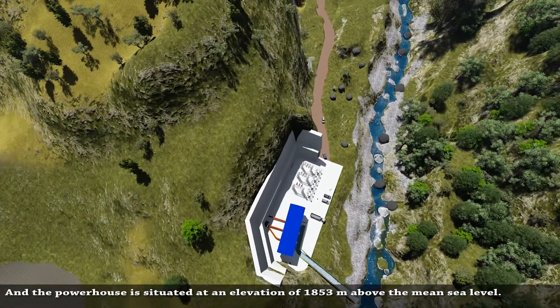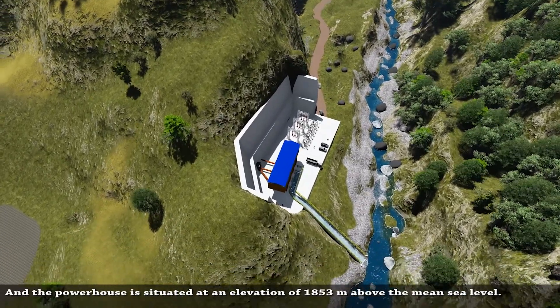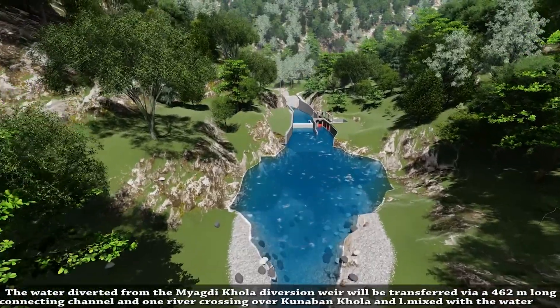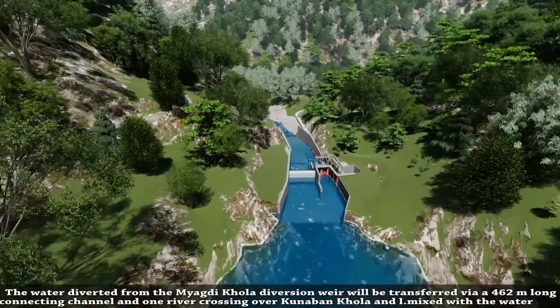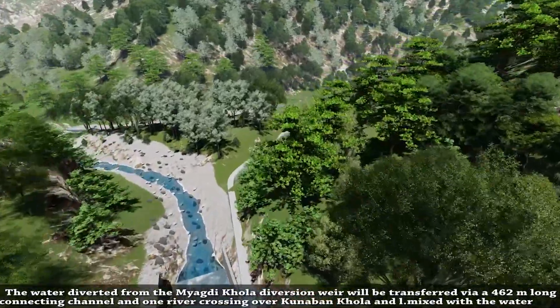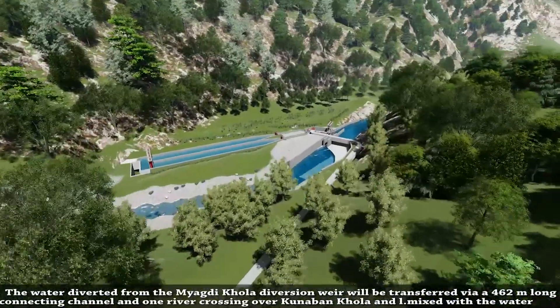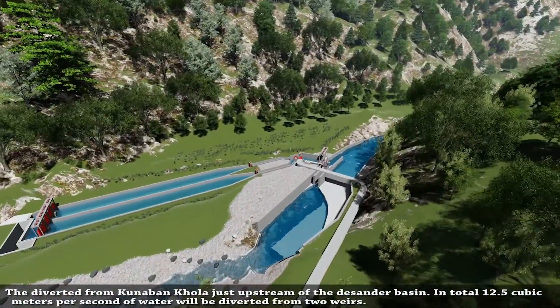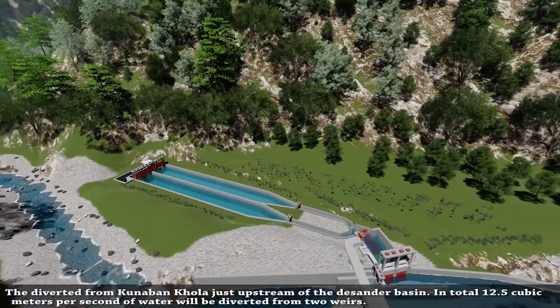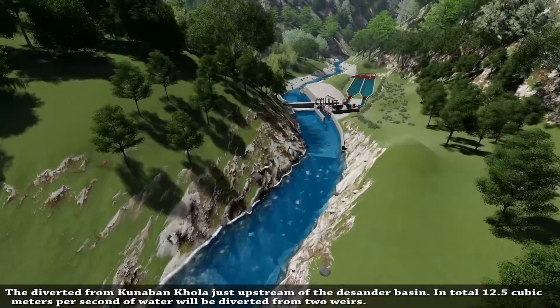The powerhouse is situated at an elevation of 1853 meters above mean sea level. The water diverted from Myagdi Khola diversion weir will be transferred via a 462-meter long connecting channel and one river crossing over Kunaban Khola, mixed with water diverted from Kunaban Khola just upstream of the desanding basin. In total, 12.5 cubic meters per second of water will be diverted from two intakes.